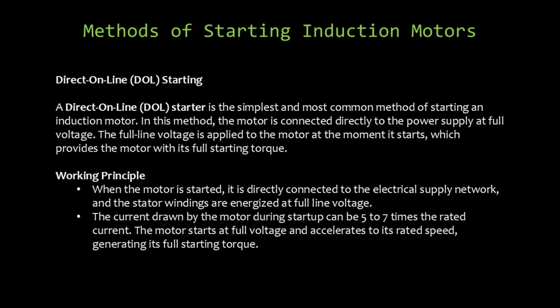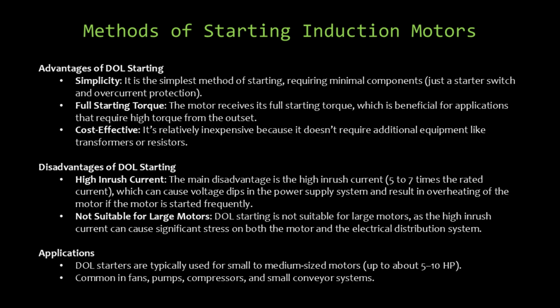The direct-on-line starting method represents the simplest approach to motor startup. In this method, the motor connects directly to the power supply at full voltage. When started, the stator windings are energized at full line voltage, allowing the motor to draw its full starting current. While providing full starting torque, this method can draw 5 to 7 times the rated current, making it ideal for small to medium-sized motors.